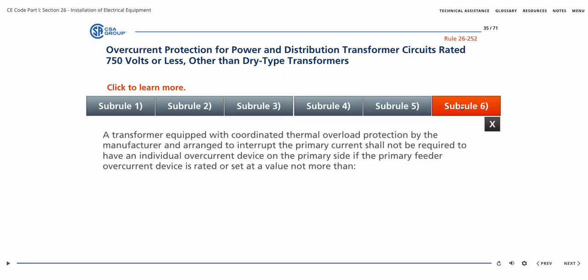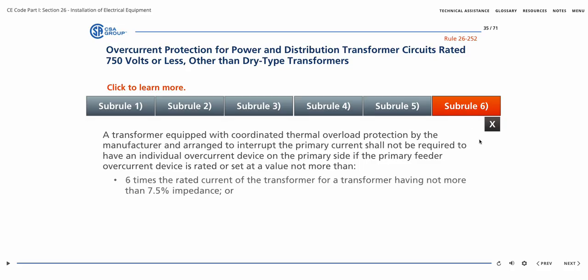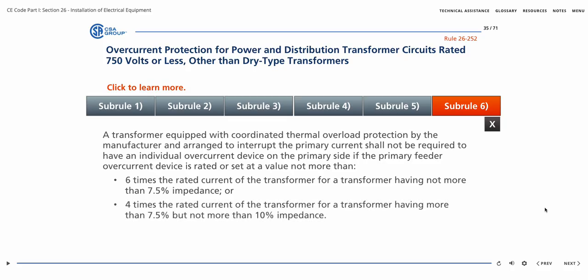Subrule 6. A transformer equipped with thermal overload protection by the manufacturer and arranged to interrupt the primary current shall not be required to have an individual overcurrent device on the primary side if the primary feeder overcurrent device is rated or set at a value not more than 6 times the rated current of the transformer for a transformer having not more than 7.5% impedance, or not more than 4 times the rated current of the transformer for a transformer having more than 7.5%, but not more than 10% impedance.